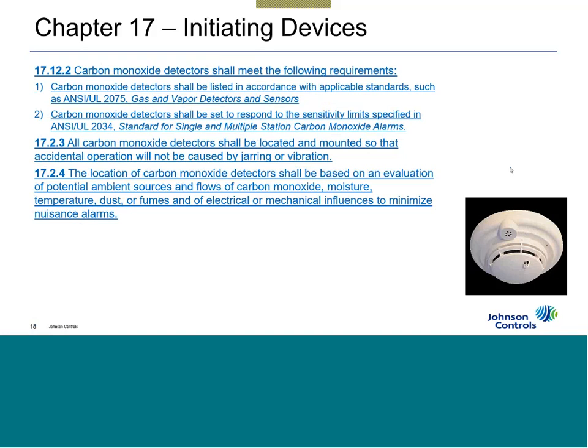So some codes will require that the carbon monoxide alarm be installed in the rooms. And you go in and say, look, I got a sensor with a base. I want to use this instead of the cheap device you buy down from Home Depot. Well, for us to be able to do that, we want the device UL listed as both. It's listed as UL 2075 for a sensor and 2034 when combined with a sounder base as a single station alarm. The same is true, side note, for smoke detectors.